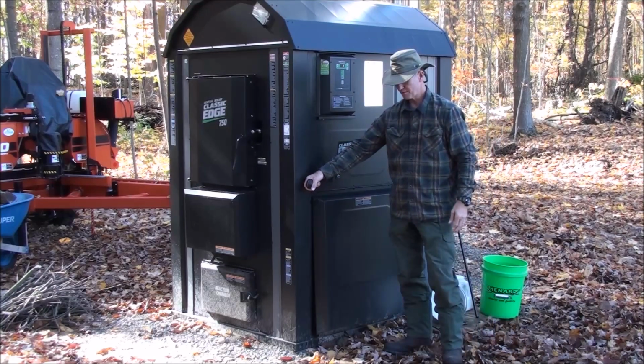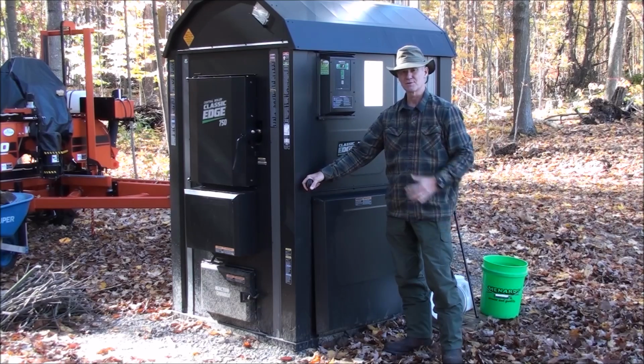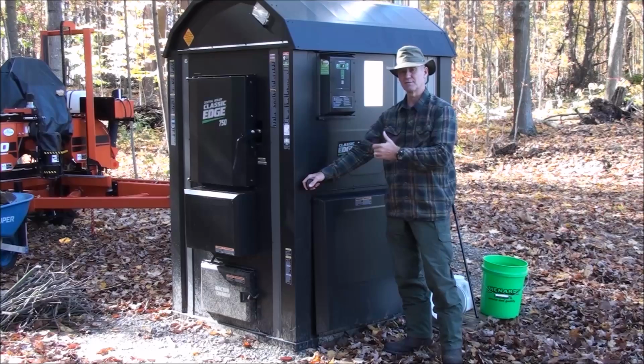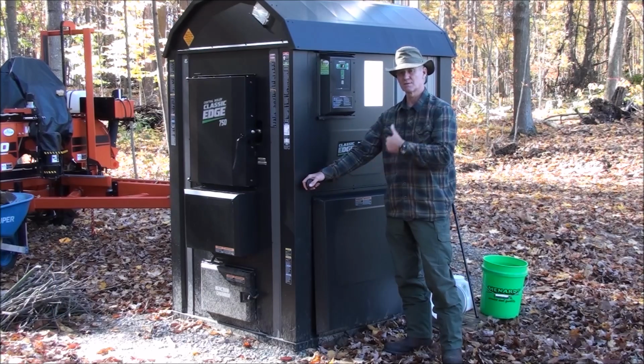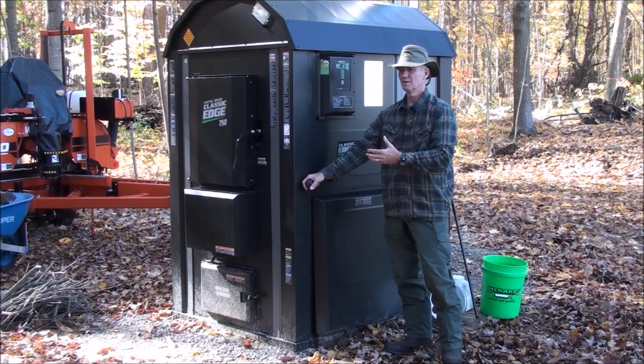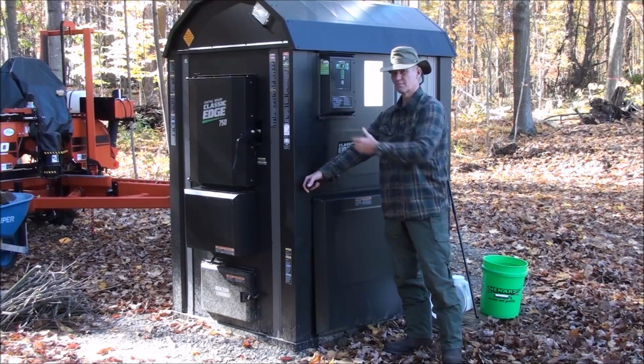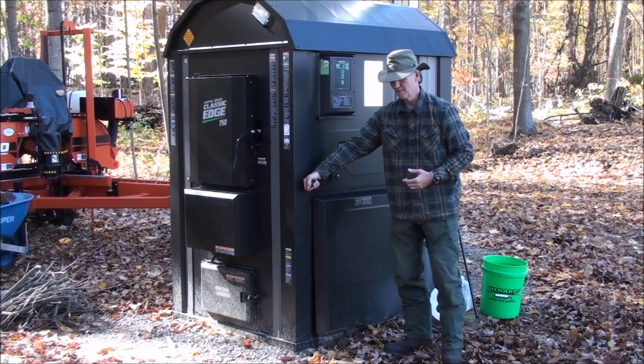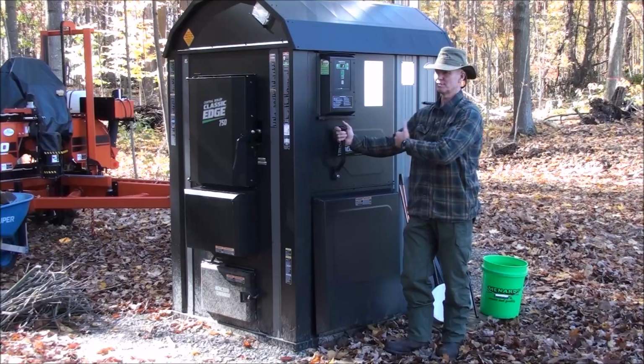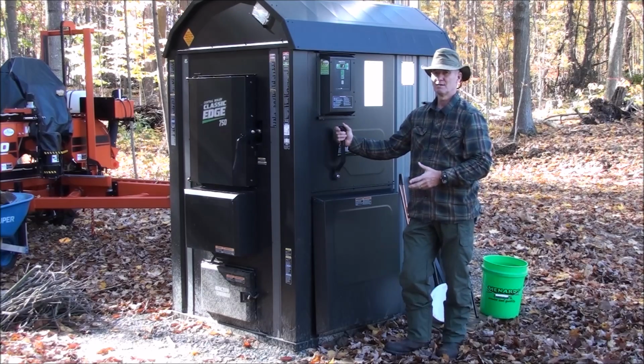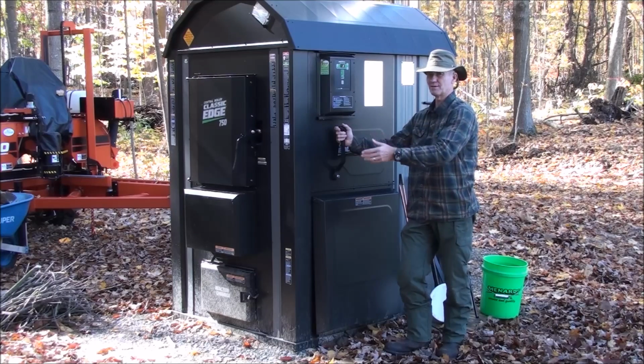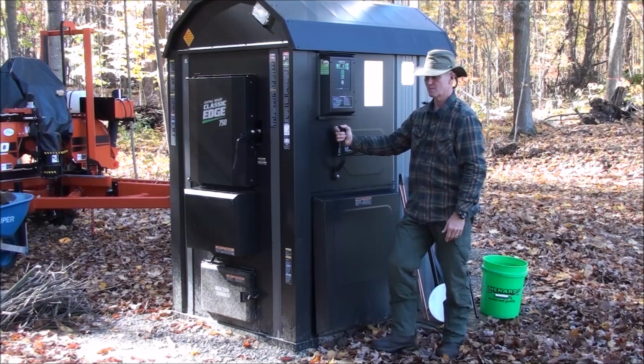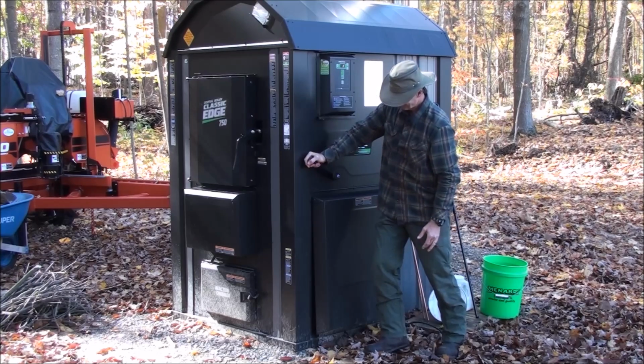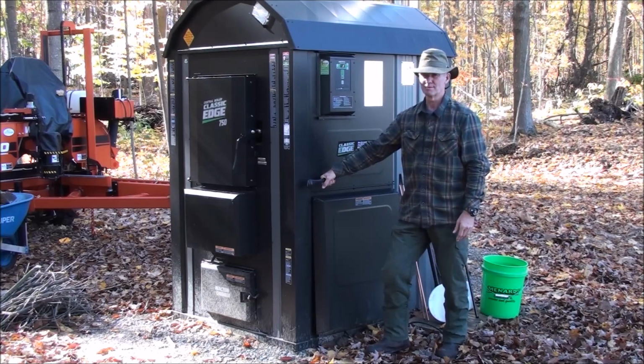And then this handle operates what's called a bypass. So when this thing is in operation, pressure will build up inside the firebox. There's blowers providing air to make the fire burn hot. So before you open the door to the firebox to add wood, you open this bypass, which relieves the pressure inside the firebox about 20 to 30 seconds before opening the door. This bypass will also be open during startup.